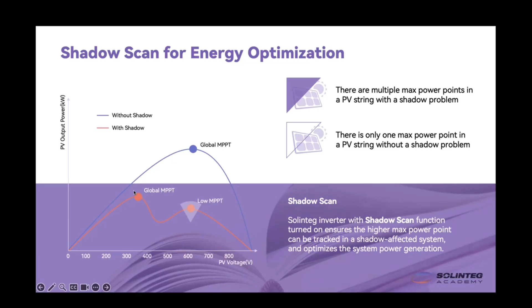But what if we have some shadows on the PV panels? In this case, the power generation curve will be like this, so it will have many max power points. And some inverters don't support the shadow scan function. That means this inverter might find a low max power point and then start to work at this point, and that means it will lose part of the PV generation. For our inverter, which supports the shadow scan function, it will keep looking until it finds the highest max power point. So the inverter will start working at that point, and we can make sure that the efficiency of the total system has been increased, and also we can optimize the system's power generation.